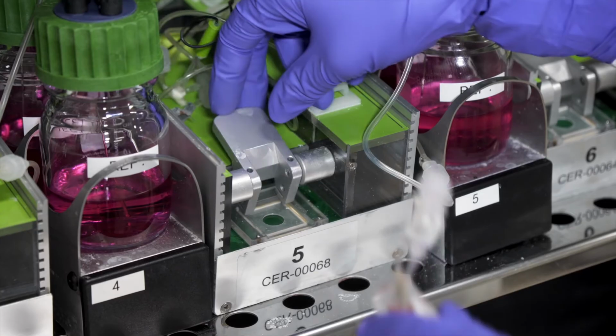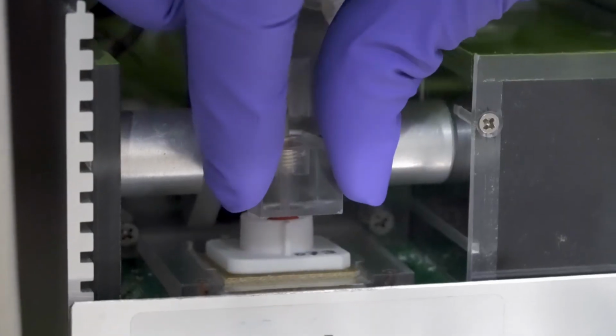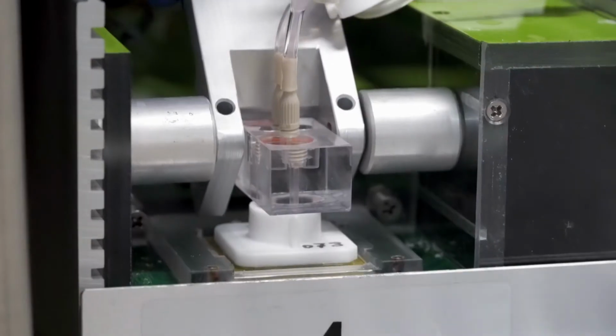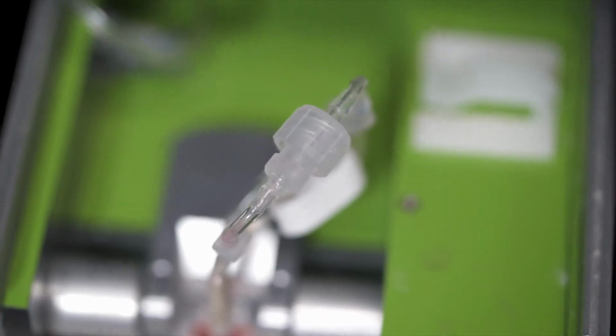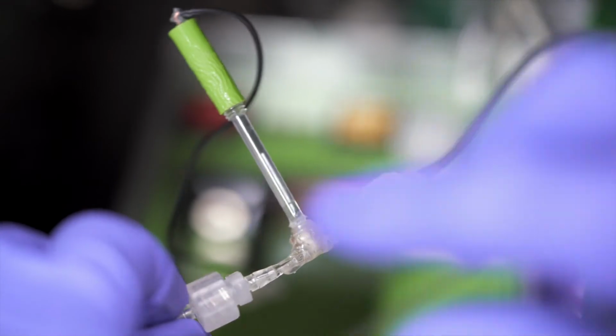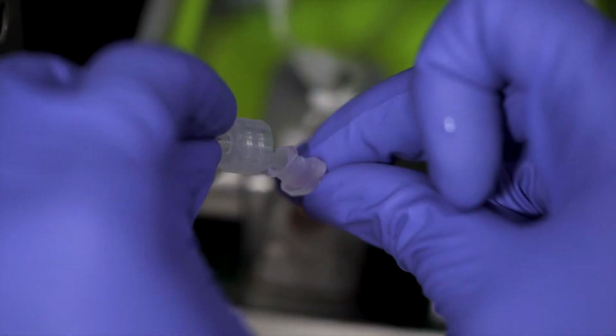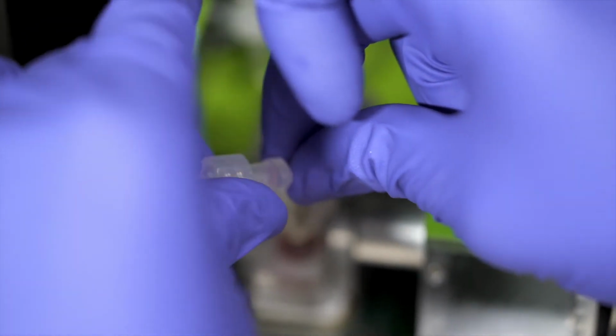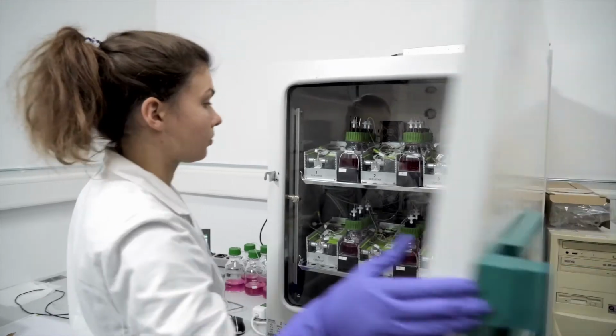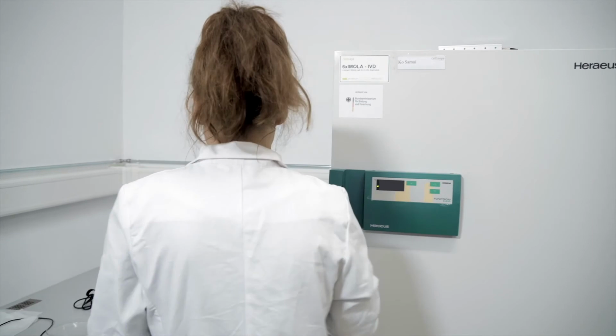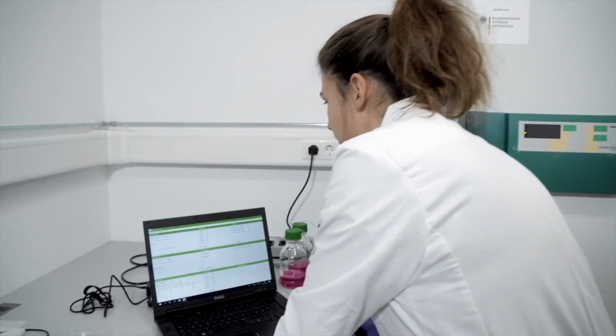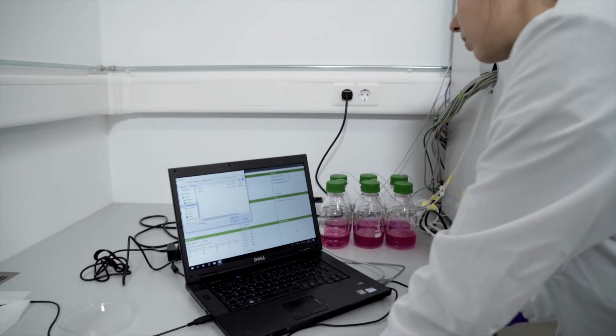To install the biochips in the IMOLA systems, open the clamp, place the biochips into the socket and close the clamp. Then, open the luer connector of the biochip and the one in front of the reference electrode and connect the biochip to the fluidic system. Please note that the biochip without any cells must not be inserted into IMOLA 1. Usually, it's placed into IMOLA 2.